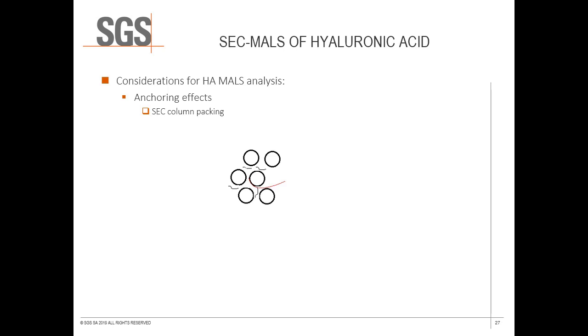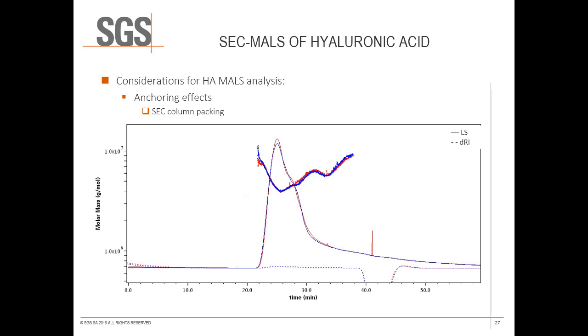As polymer molecules pass through the beads of the column packing, very large chains tend to anchor. This may lead not only to extreme tailing and a lack of separation based solely on size, but also shear degradation for the polymer. This is exemplified in strongly tailing SEC peaks, such as the one shown. Molar mass plots may curve up significantly in the tail of the peak when anchoring occurs. Again, using columns with large particle diameters and pore sizes helps to reduce anchoring.